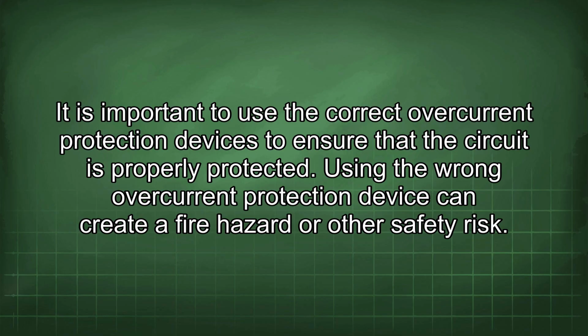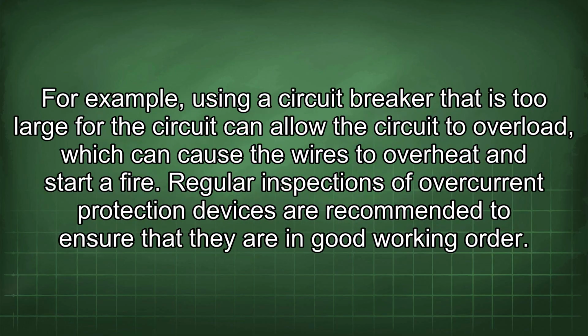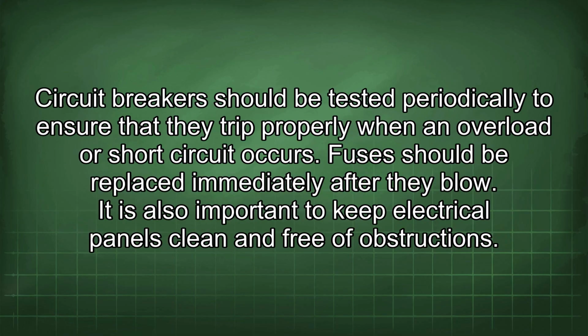It is important to use the correct overcurrent protection devices to ensure that the circuit is properly protected. Using the wrong overcurrent protection device can create a fire hazard or other safety risk. For example, using a circuit breaker that is too large for the circuit can allow the circuit to overload, which can cause the wires to overheat and start a fire. Regular inspections of overcurrent protection devices are recommended to ensure that they are in good working order. Circuit breakers should be tested periodically to ensure that they trip properly when an overload or short circuit occurs. Fuses should be replaced immediately after they blow.